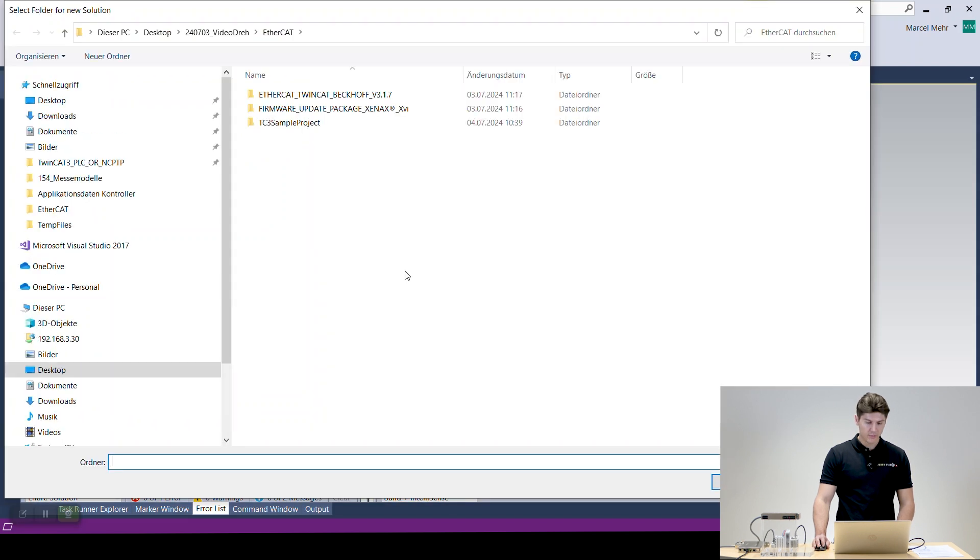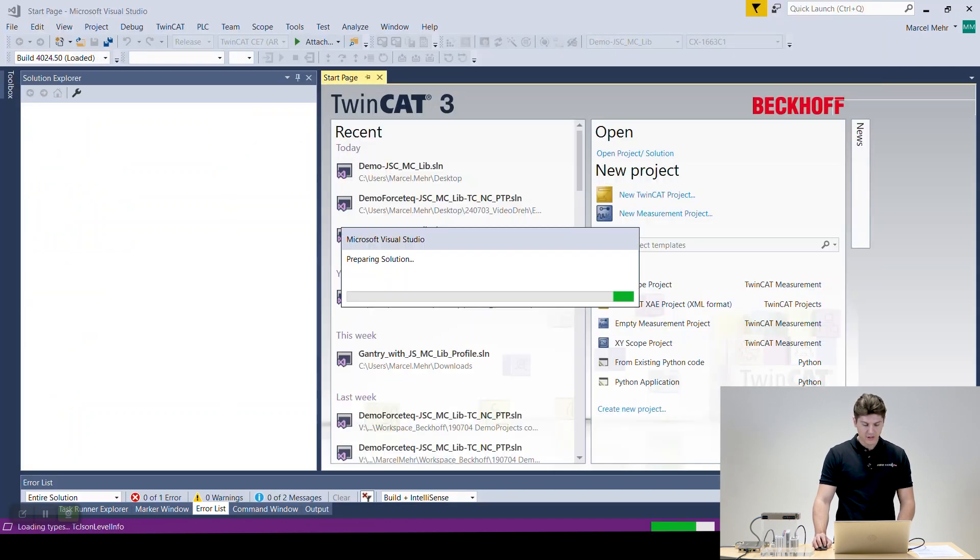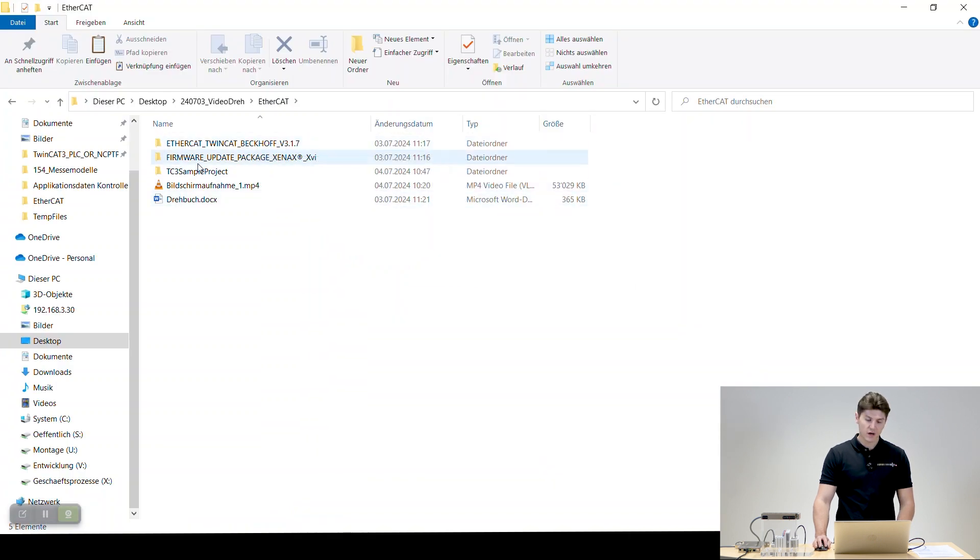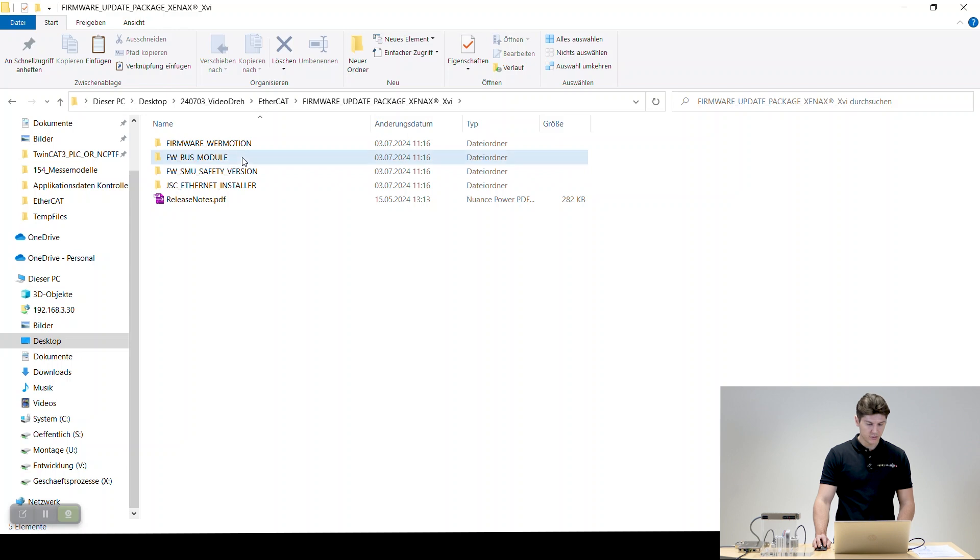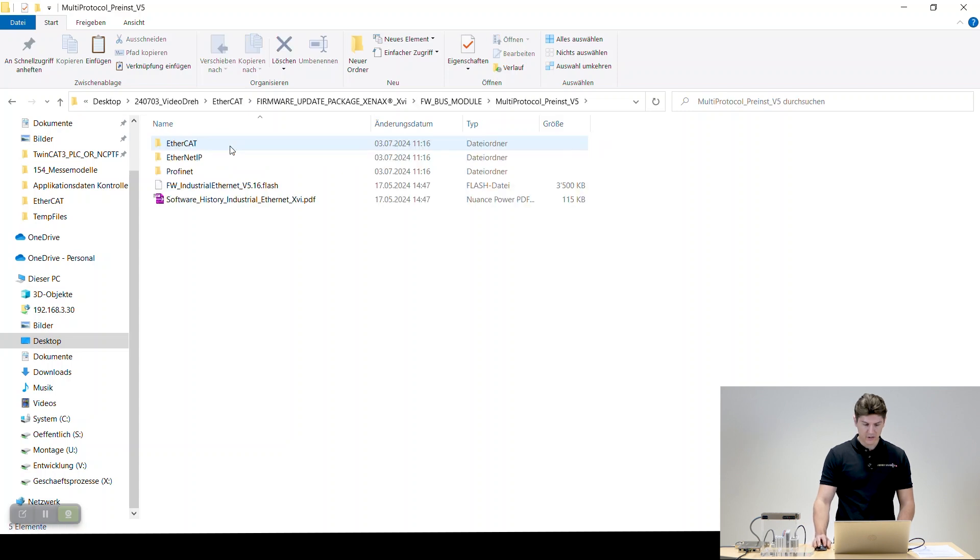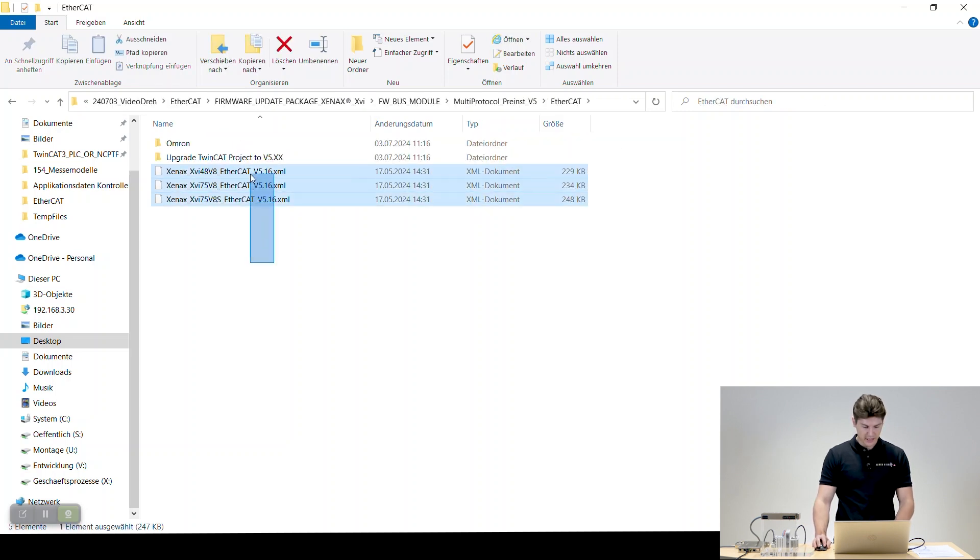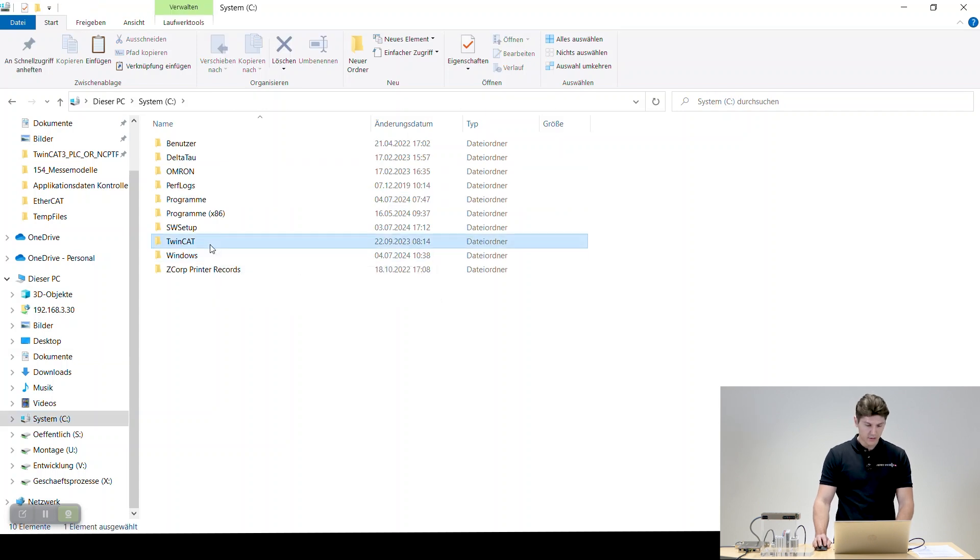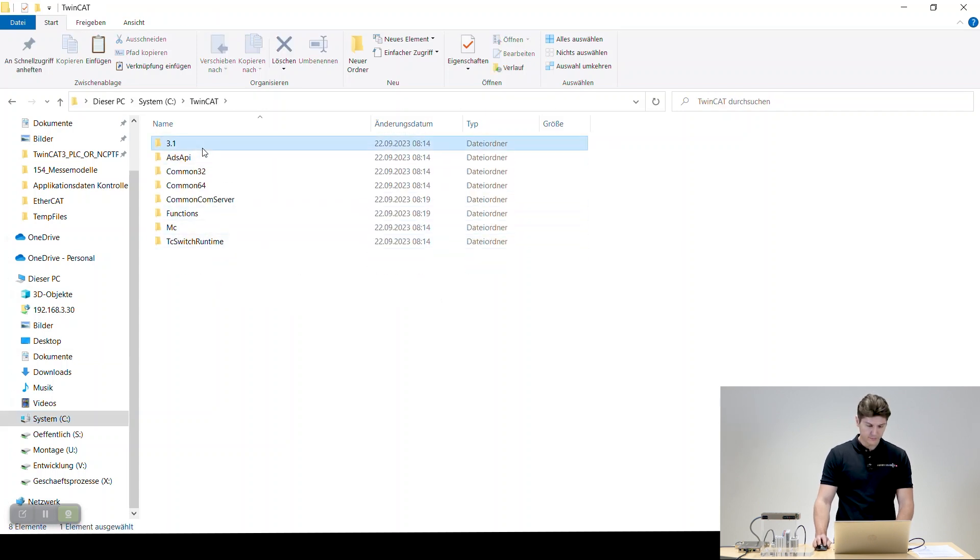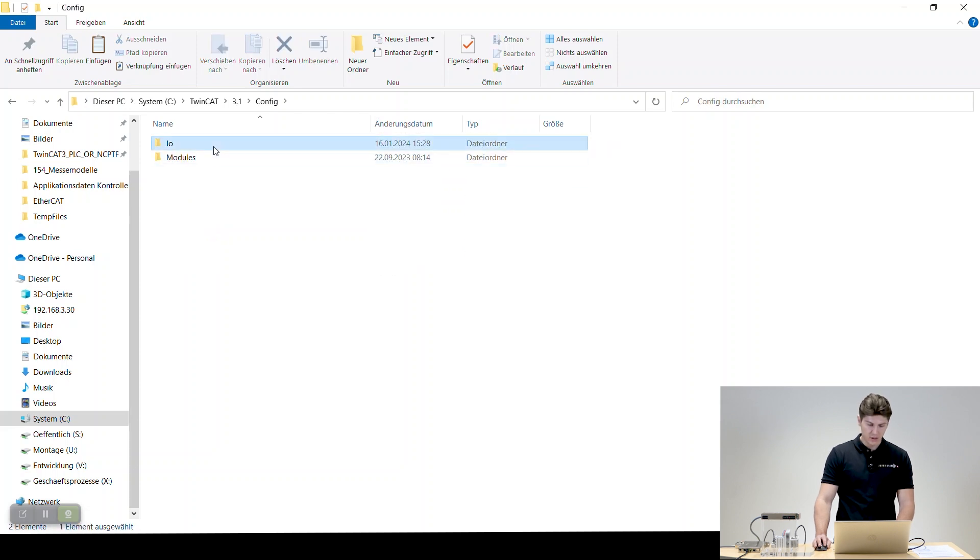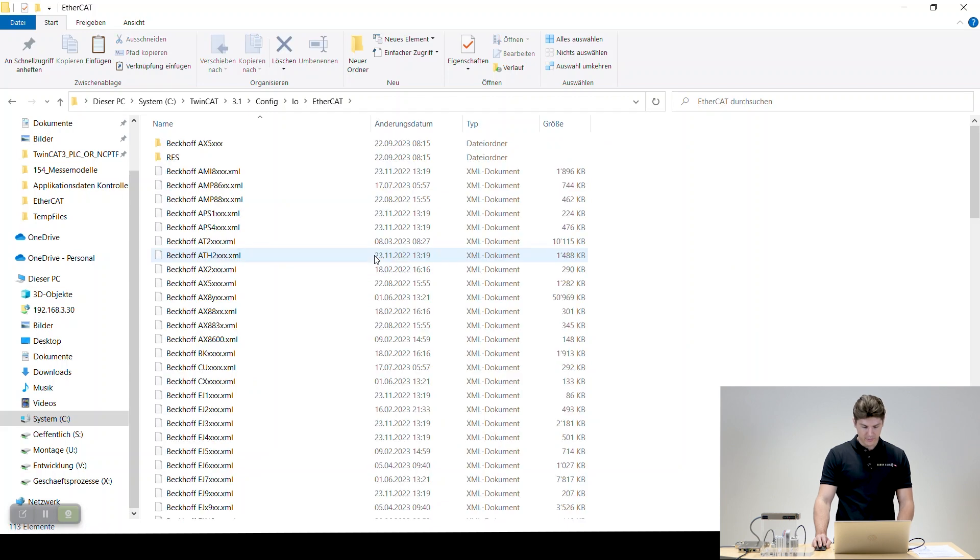We open that up and then we say where we want to store it. So while this is opening we can start and install our XML files. You find that in the firmware update package, download firmware, bus module. Then you go multi-protocol, that's what we have installed here, EtherCAT, and you're going to copy those XML files. Then you go into your install folder of your TwinCAT, 3.1, then config, IOs, and then into EtherCAT and here you place them in.